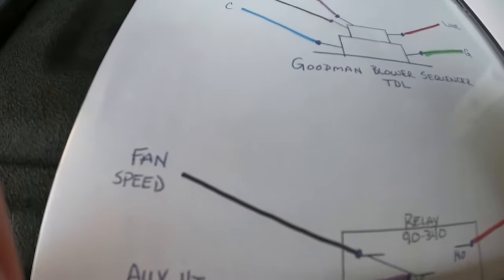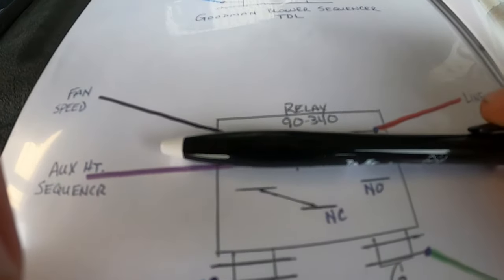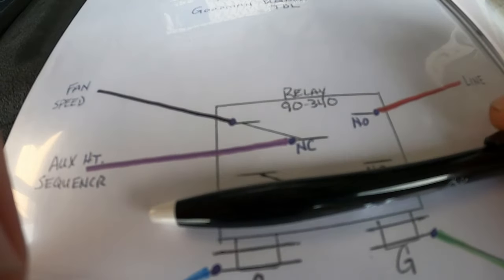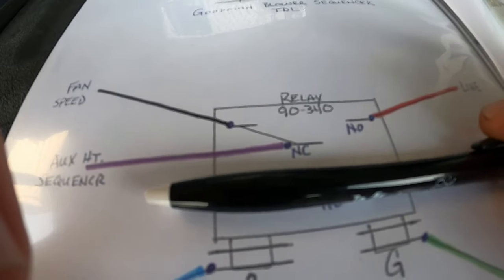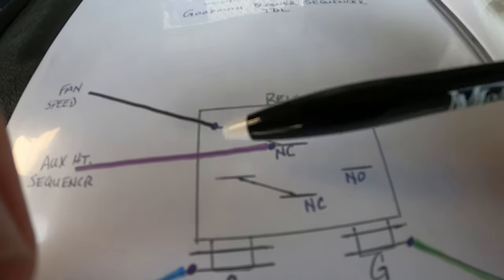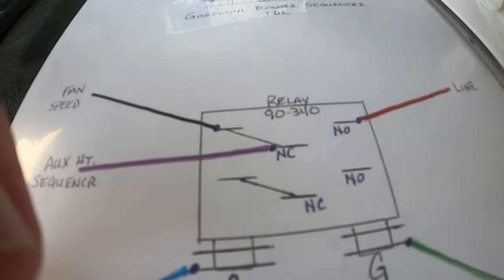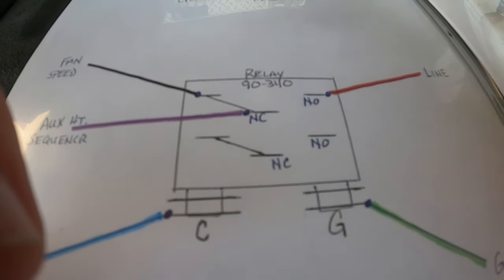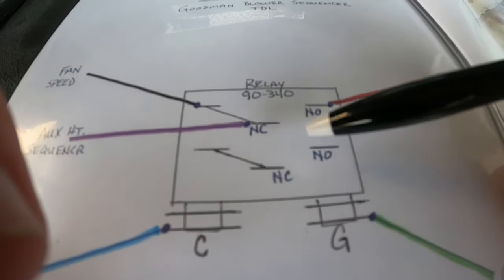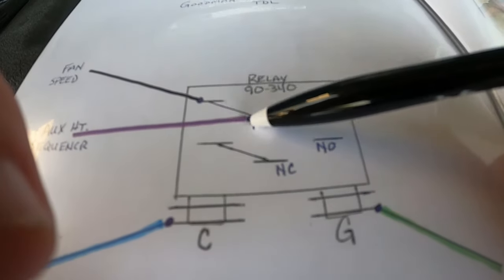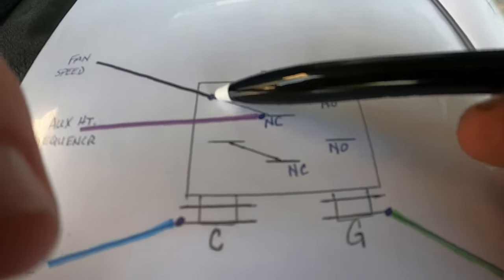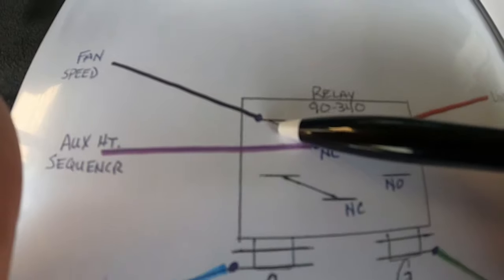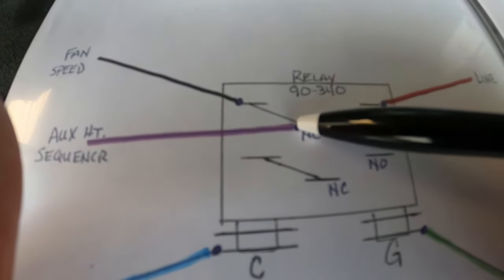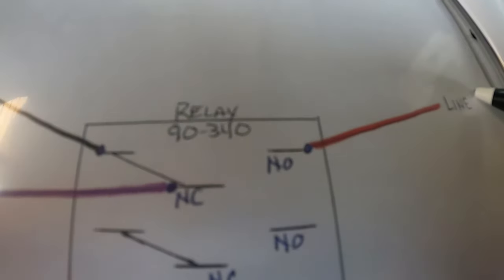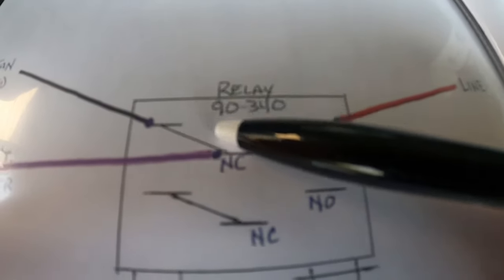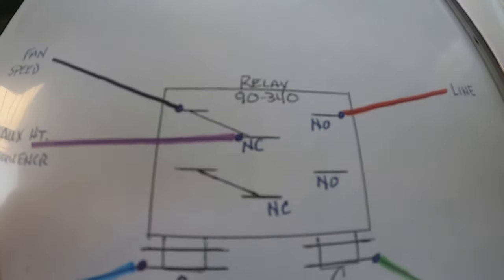This particular switch is not used because there's two switches on this relay. That's why I say double pole, double throw. You've got two switches on it, and you've got two poles, a common pole there and a common pole there. So when this energizes, this pole, which is going to be your fan speed there, is going to switch to your line voltage in here, and then that's going to power your blower during normal heat pump or cooling operations.